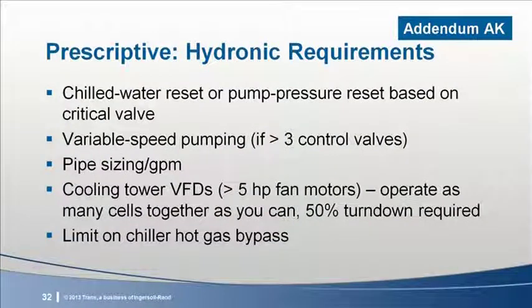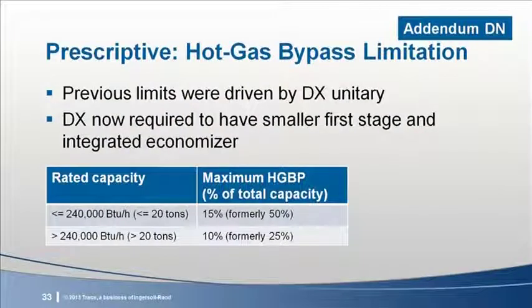And how much you're pumping matters too. Pipe sizing limits in the form of GPM per pipe size ensure that excessive pump pressure and pump energy is avoided. Cooling tower fans larger than 5 horsepower are required to have VFDs or similar performance, and the new part is that VFDs are required to be operated together across all operating cells, and that towers have a 50% turn down capability. Another new change that kind of flew under the radar with respect to chillers is the new lower limit on hot gas bypass. This is a design element for chillers that has a valve that can open at low load to false load the compressor and keep the chiller either away from surge or keep the chiller idling online while its application prefers that the chiller not turn off, usually at very low load conditions.